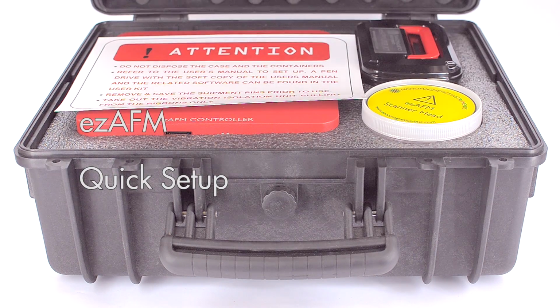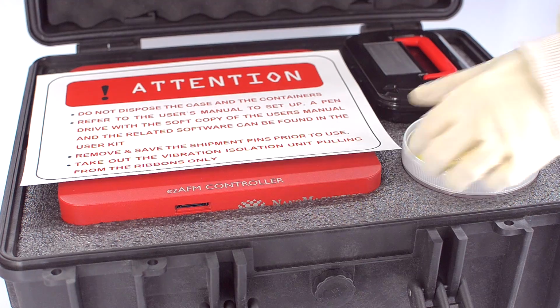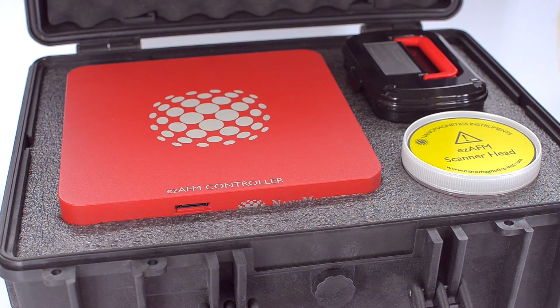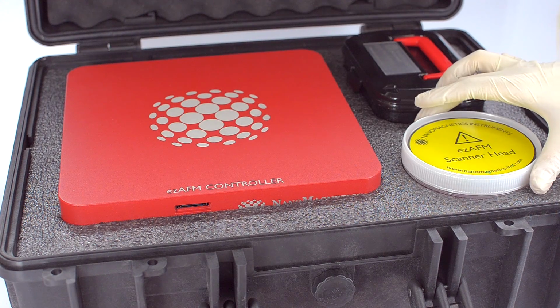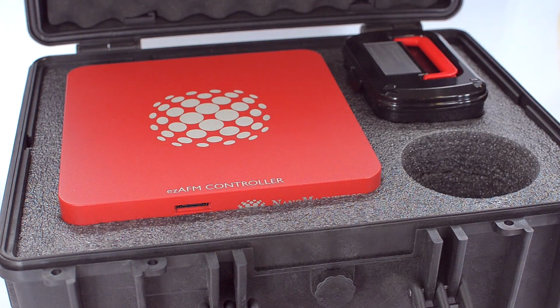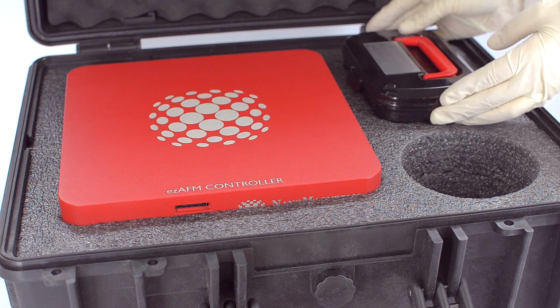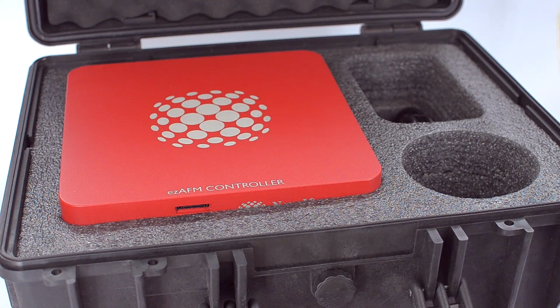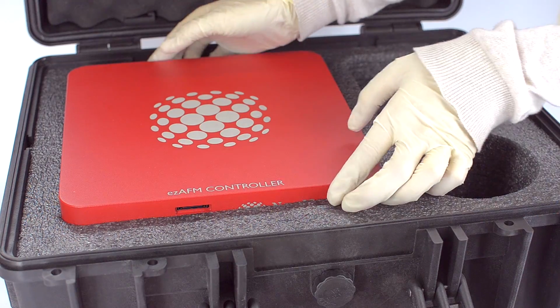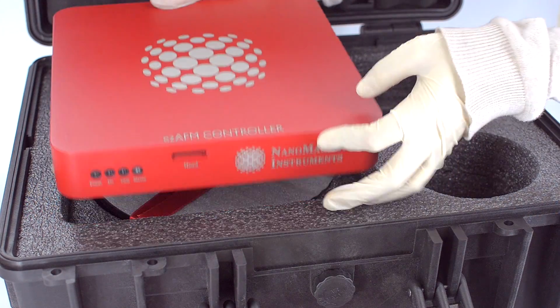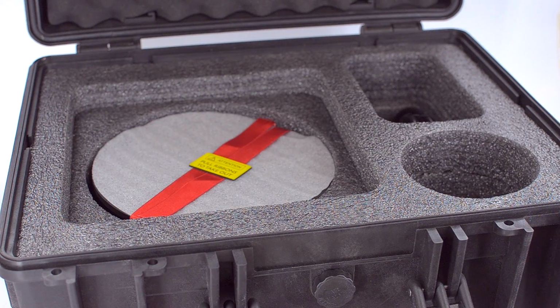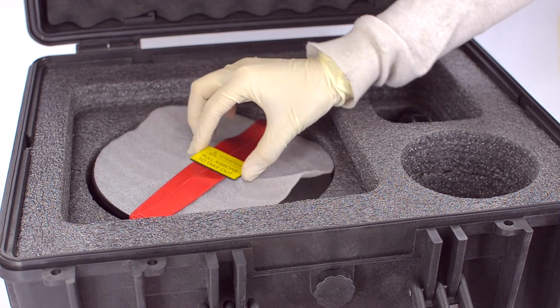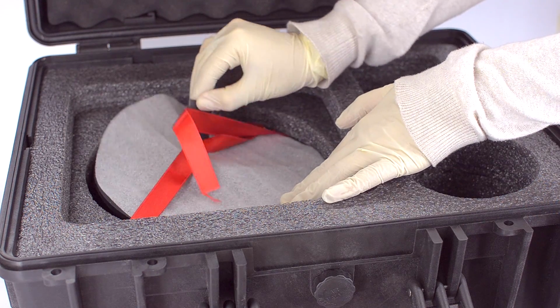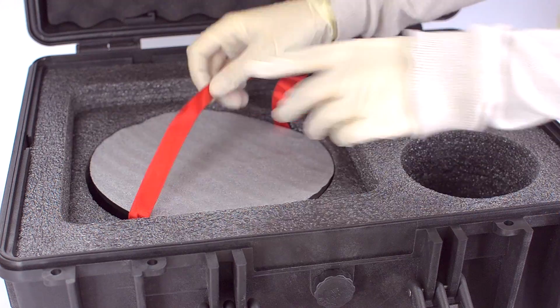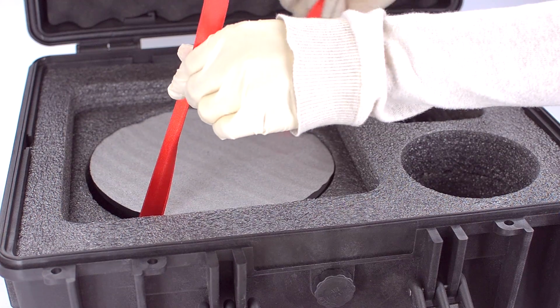ezAFM is a compact tabletop AFM system. Setting up the ezAFM is very easy. Remove the scanner head, the user kit, and the ezAFM controller. To remove the vibration isolation platform, detach the ends of the ribbon and gently lift the vibration isolation platform.